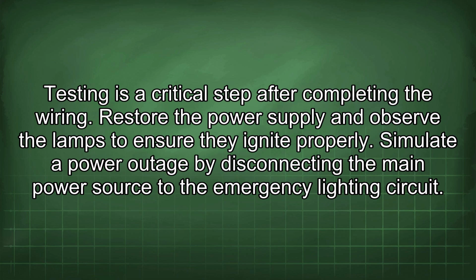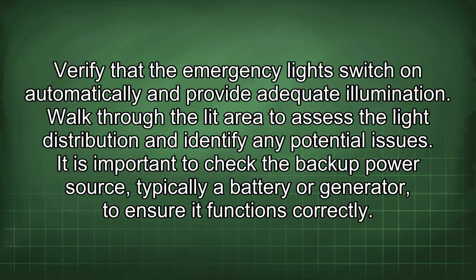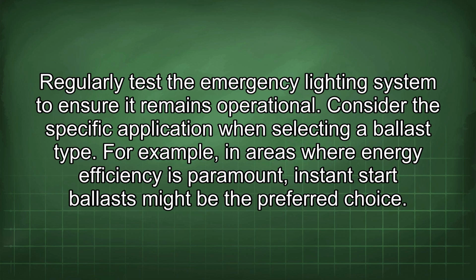Testing is a critical step after completing the wiring. Restore the power supply and observe the lamps to ensure they ignite properly. Simulate a power outage by disconnecting the main power source to the emergency lighting circuit. Verify that the emergency lights switch on automatically and provide adequate illumination. Walk through the lit area to assess the light distribution and identify any potential issues. It is important to check the backup power source, typically a battery or generator, to ensure it functions correctly. Regularly test the emergency lighting system to ensure it remains operational.